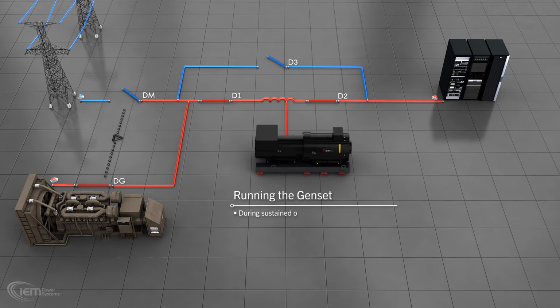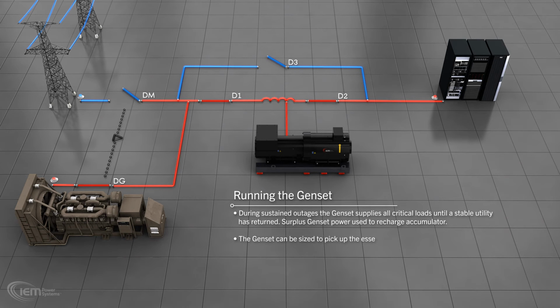Running the genset. During sustained outages, the genset supplies all critical loads until a stable utility has returned. Surplus genset power is used to recharge the accumulator. The genset can be sized to pick up the essential loads after a short break.